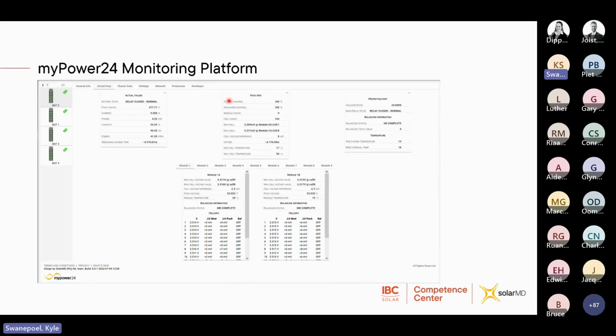And over here you can get an overview per battery again. So if there is a battery that is limiting the charge or the discharge, it will report that information over here under your charge and discharge control. So for those of you that are using the loggers to view the low voltage batteries, all of this is exactly the same. It's just, like I mentioned, this number is smaller, but your cell data is exactly the same with the delta over here, and your charge and discharge control levels are also based off a percentage. 100% means that full values are being sent from this battery. So it's full current limit and it's full voltage limit. And when it reaches the top end from charge or the bottom end from discharge, these will start to limit and then send limiting information to the inverter to either stop the discharge or stop the charge.